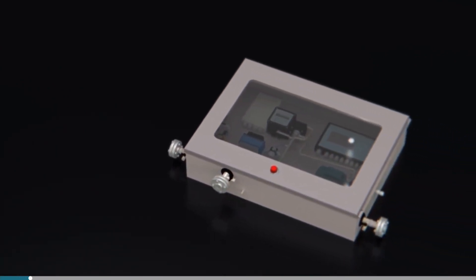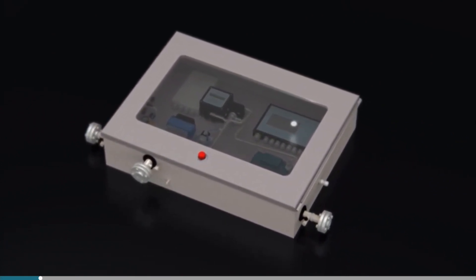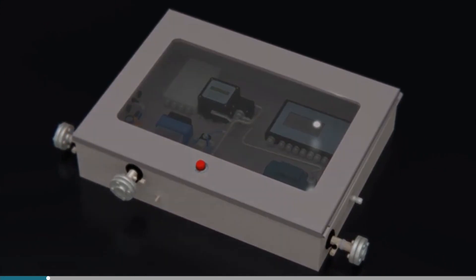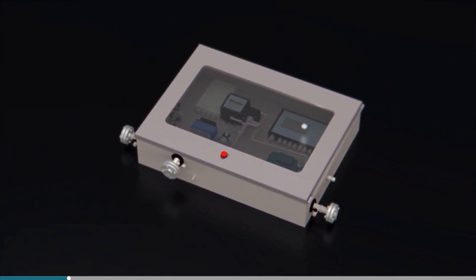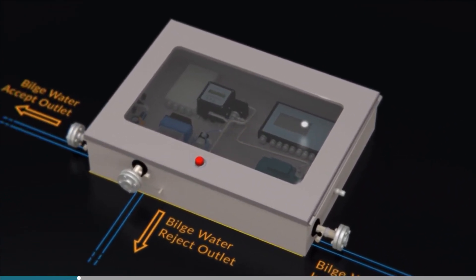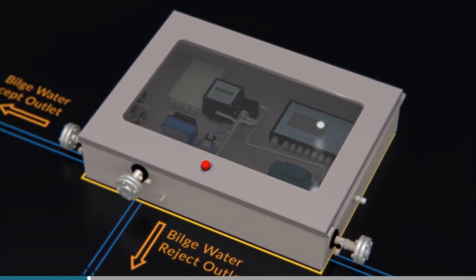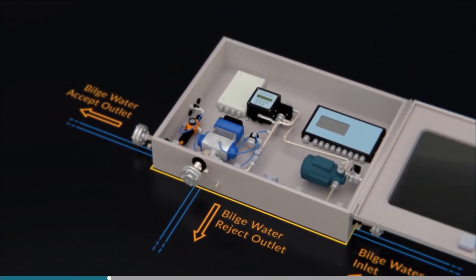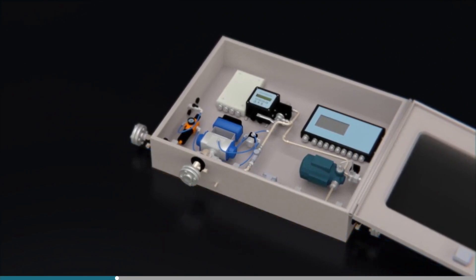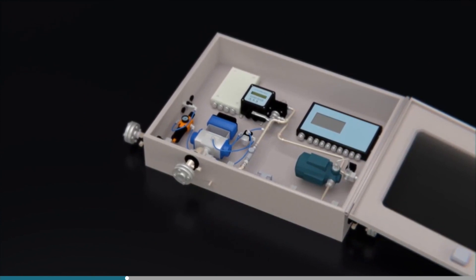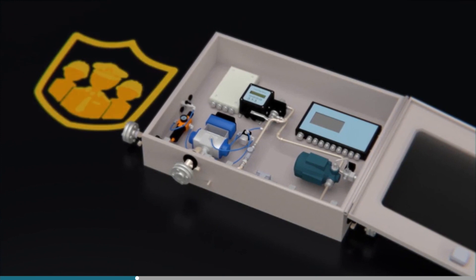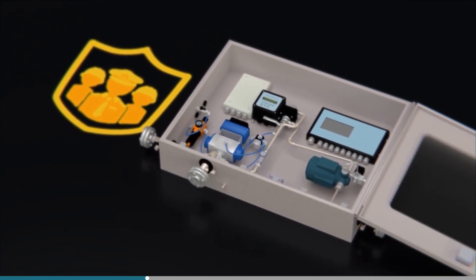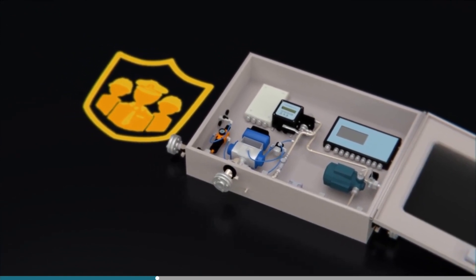This chapter discusses the Marinfloc IMO white box system. The white box system was designed to protect you, the rest of the crew, and the ship owner. It was developed by Marinfloc as a fail-safe system for the discharge of water overboard, intended to prevent water with too high an oil content from being accidentally pumped overboard. It can function as an ODME system as required for tankers, but may also be fitted on other types of vessel. To help prevent tampering, all of the equipment is built into a lockable cabinet called the white box, providing evidence that operations have been legal and that there has been no tampering with the equipment.